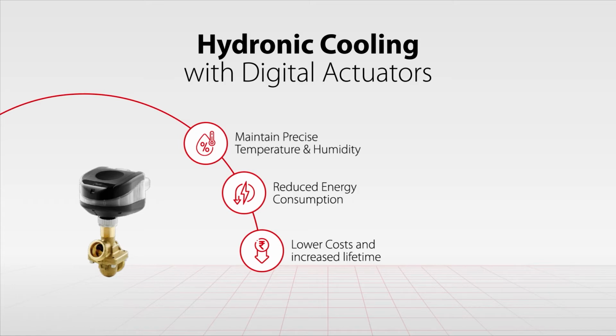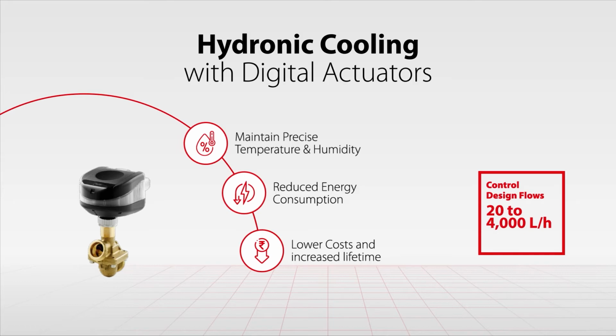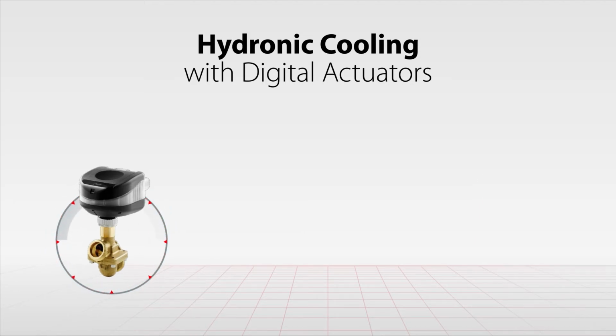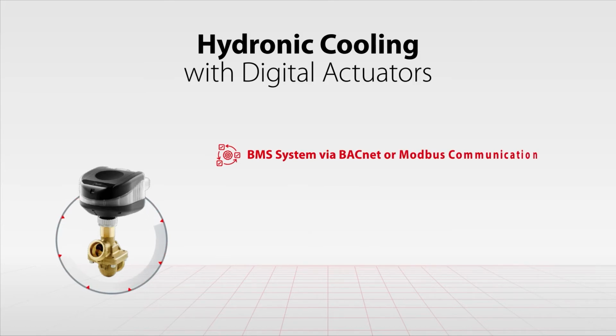The ABQM controls the required flow of water across terminal units such as AHUs, FCUs, and radiation panels with an integrated differential pressure controller to maintain hydronic balance and precision system temperature. It also enables IoT-driven energy-efficient solutions to smartly control design flows between 20 and 4,000 liters per hour through terminal units. Novocon actuators share over 80 valuable data parameters with the BMS system via BACnet or Modbus bus communication, which provides a never-before level of flexibility and opportunities to analyze any irregularities and helps minimize data center downtime.